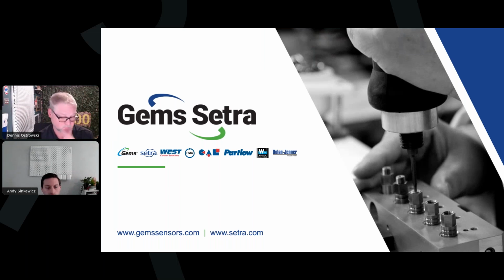Awesome. Right, another question. Why are 1/4 and 2-inch not available? Keyence has those options. Not saying that we never will, but right now the flow rates that can be measured with this device limited us to 3/8 through 1.5 inch. They had to make a decision on where to stop, and the commonality of the pipe sizes that we do offer was what they decided on, based on the commonality they found in the field in the applications and markets that we are focusing on.